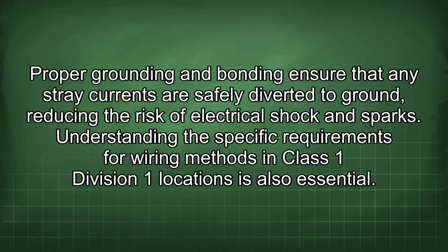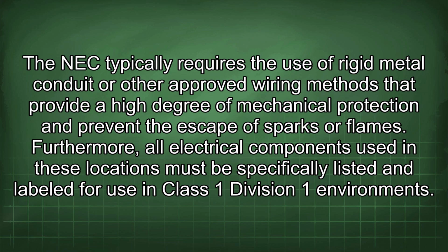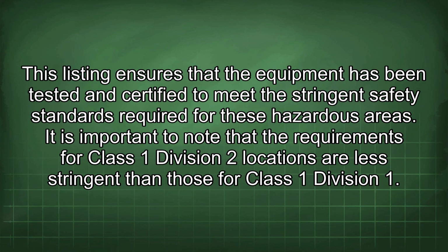Understanding the specific requirements for wiring methods in Class 1 Division 1 locations is also essential. The NEC typically requires the use of rigid metal conduit or other approved wiring methods that provide a high degree of mechanical protection and prevent the escape of sparks or flames. Furthermore, all electrical components used in these locations must be specifically listed and labeled for use in Class 1 Division 1 environments. This listing ensures that the equipment has been tested and certified to meet the stringent safety standards required for these hazardous areas.